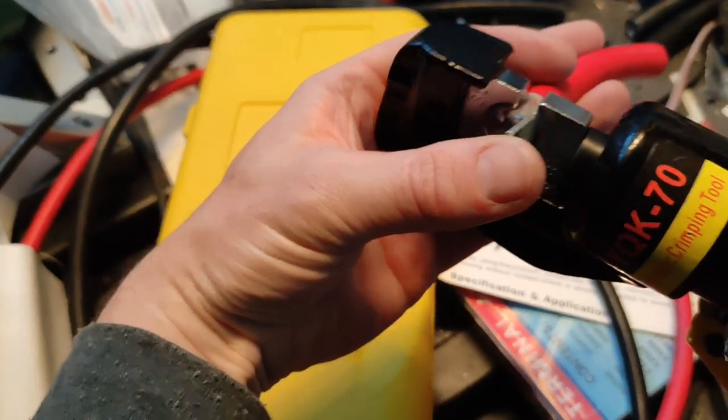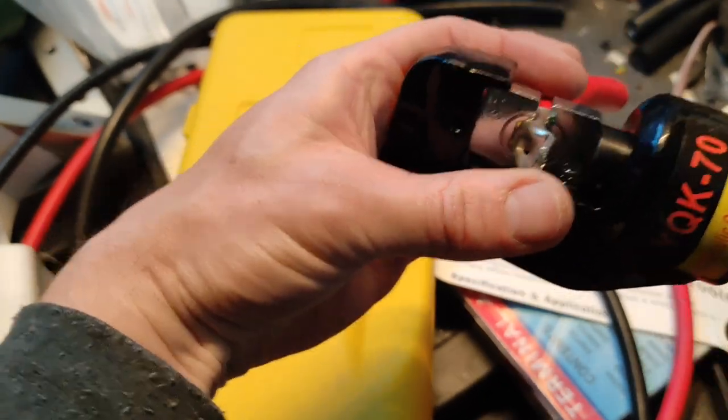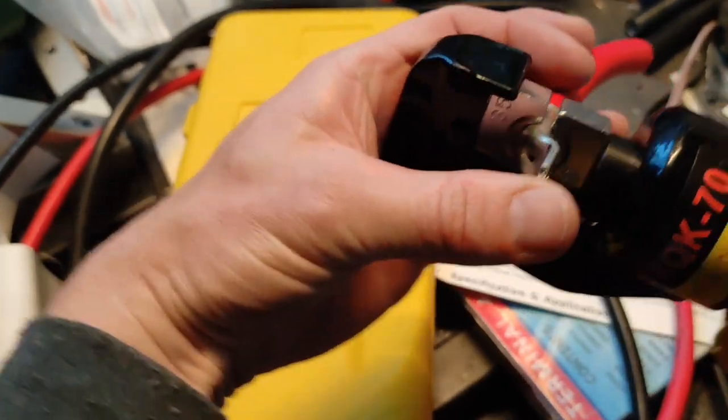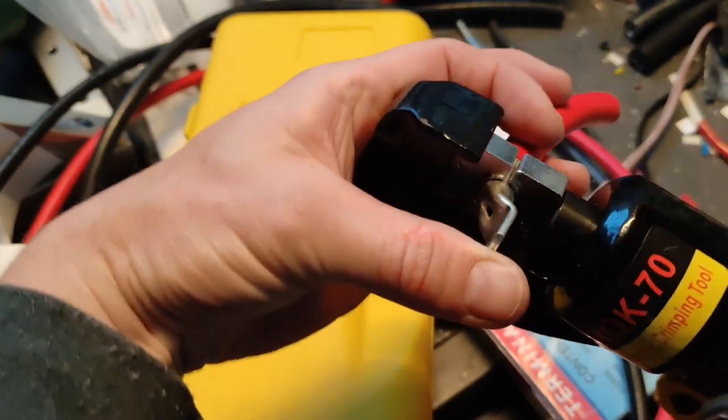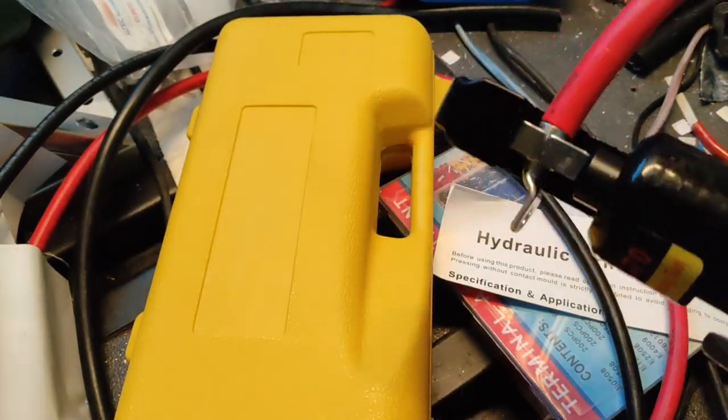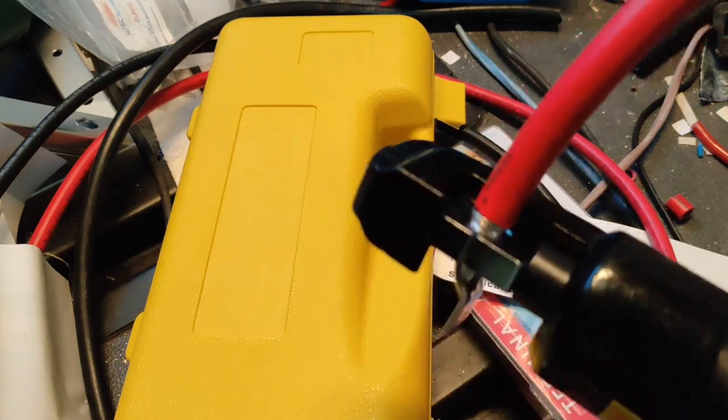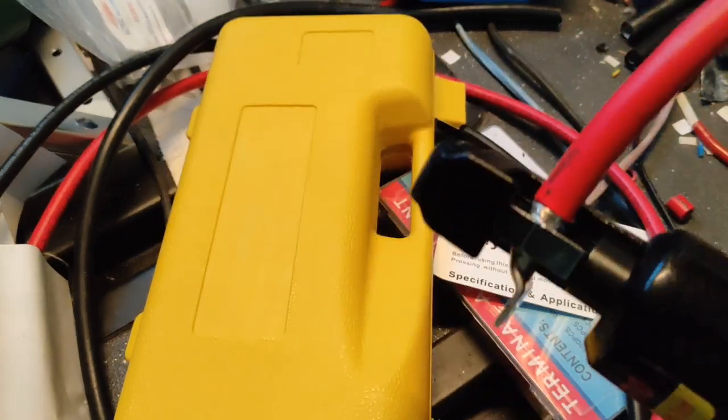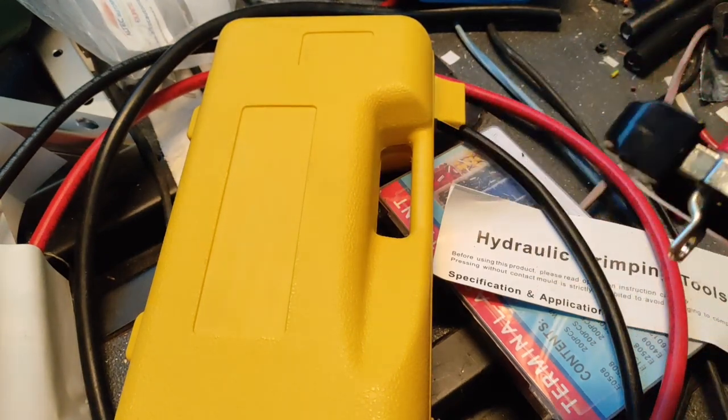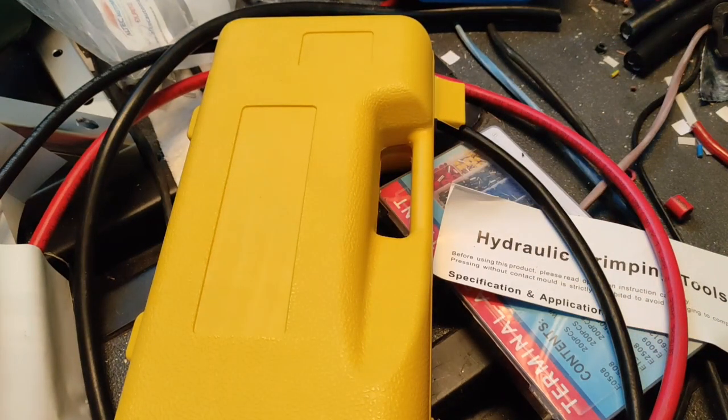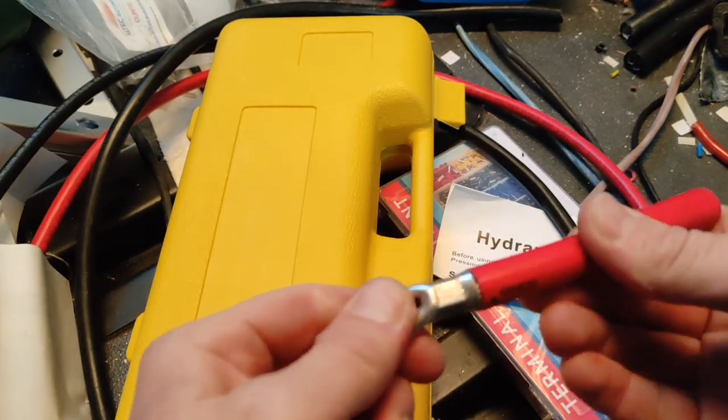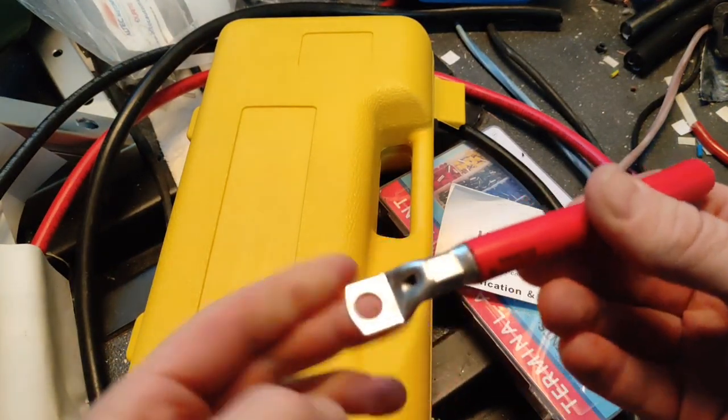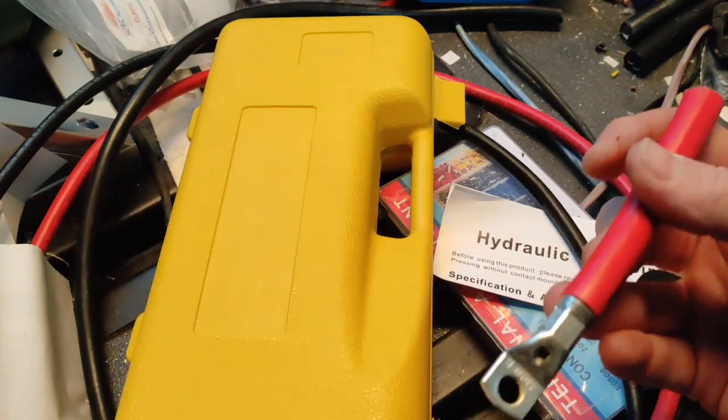So as per the last time, trying to keep it all nicely together until it grips, and then just crimping it down until the jaws come together. Okay, that's looking better. Pull test, this time that passes. So that's a good crimp, now to do the other end.